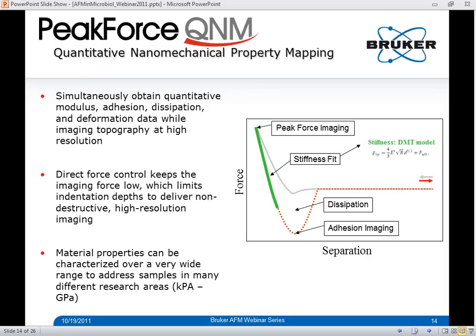The next question: is it possible with Bruker AFMs to collect images with 1024 pixels per line and 256 lines instead of square pixel images? Yes, you actually can. The majority of the FastScan data shown in the movies was actually collected at 1024 by 256, so non-square pixel images are possible.